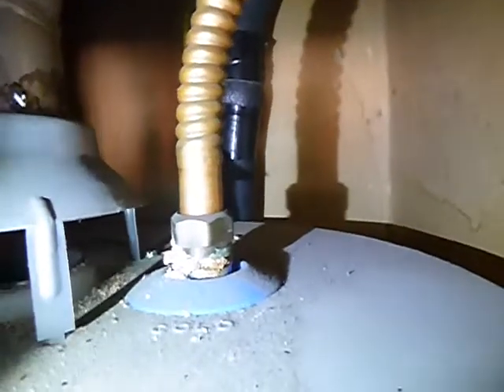We don't have a safety pan. We do not have a sediment trap. It's 10 years old, and we've got corrosion on the fittings because it's 10 years old.